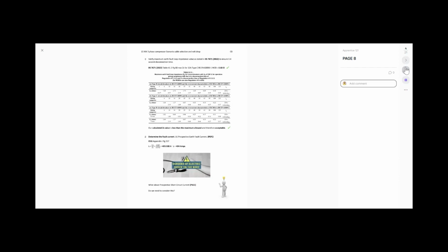So another thing to consider, and we won't do it this week, but do we need to consider our prospective short circuit current, PSCC? Do we need to consider this? We check this to make sure there's enough current to disconnect our device within a certain time under earth fault conditions. Do we need to consider it under short circuit fault conditions? I mean, we're all used to doing earth fault loop impedance tests and values and all the rest of it, but do we ever do a line neutral or a short circuit test to ensure the device is going to disconnect? I certainly know that 2396 expands upon calculating short circuit, don't they, Craig?